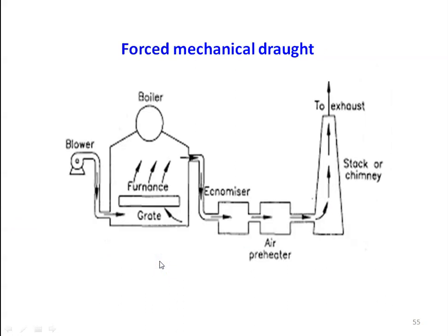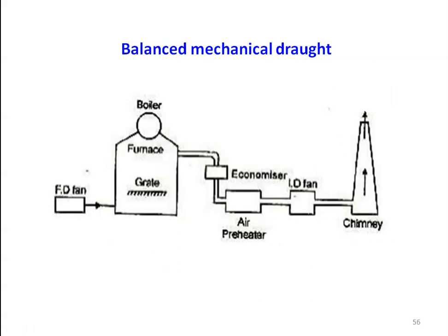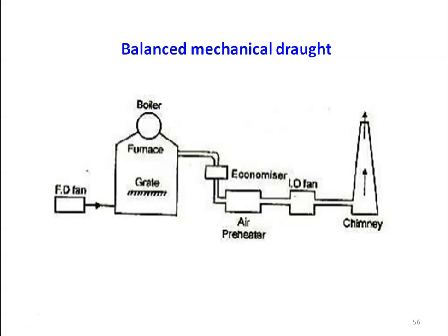To manage the drawbacks of both induced and forced draught, we install the balanced mechanical draught system, where both the FD fan (forced draught fan) and the ID fan (induced draught fan) are installed. The FD fan forces air through the grate, economizer, and air preheater, while the ID fan draws the flow and supplies the hot gases to the atmosphere via the chimney. So in balanced draught, two fans are used: one FD fan and one ID fan.